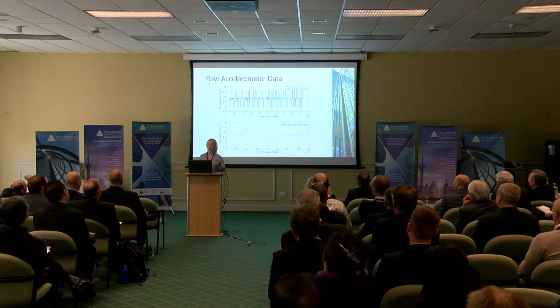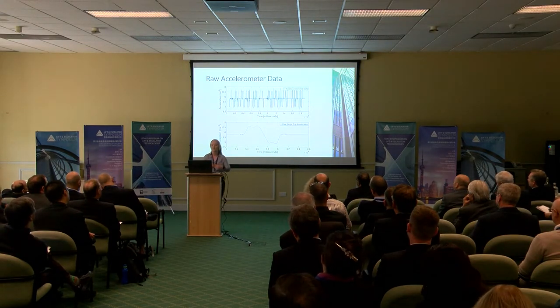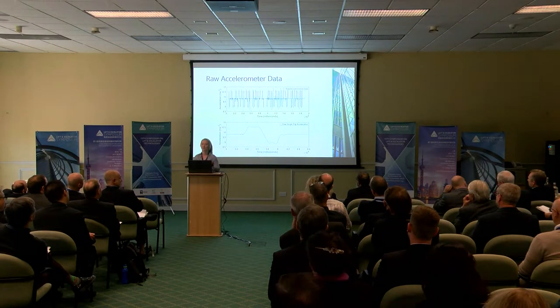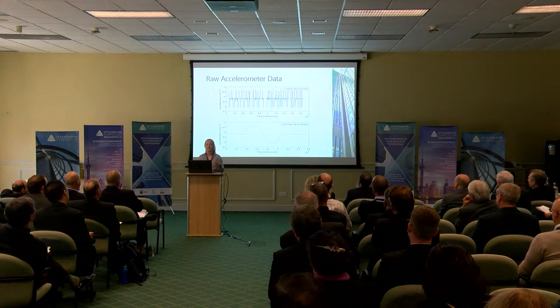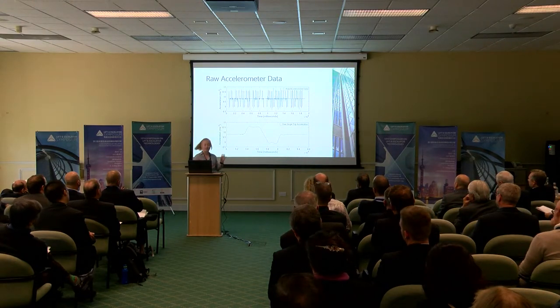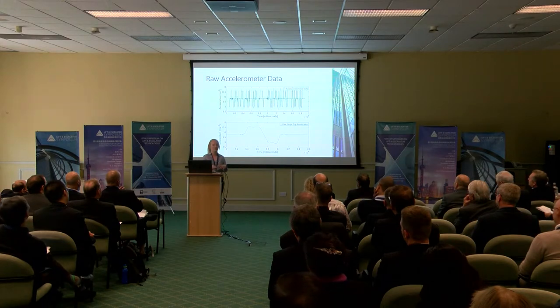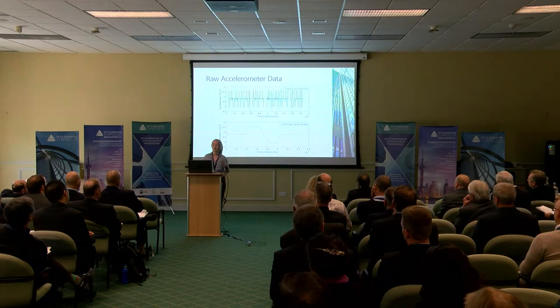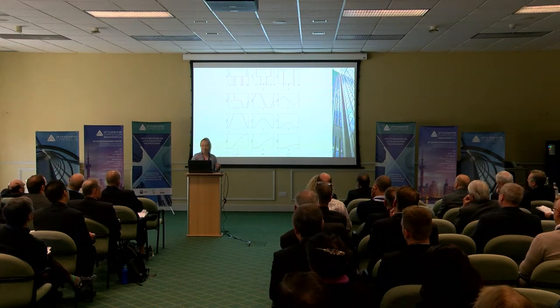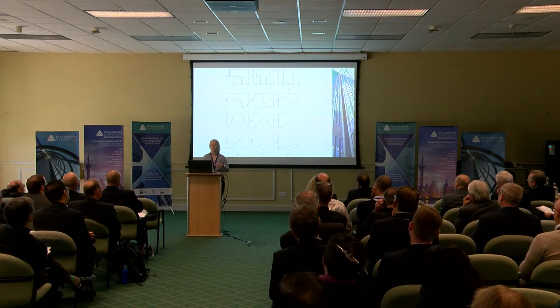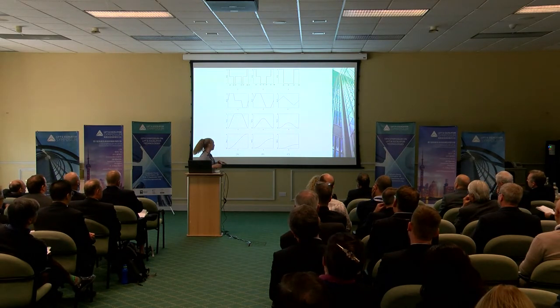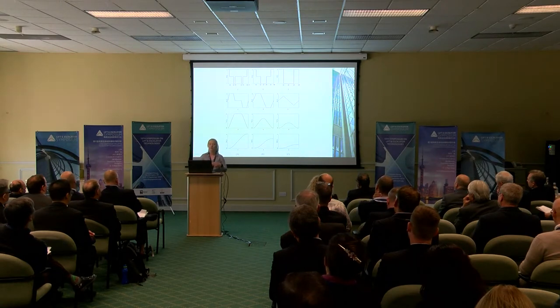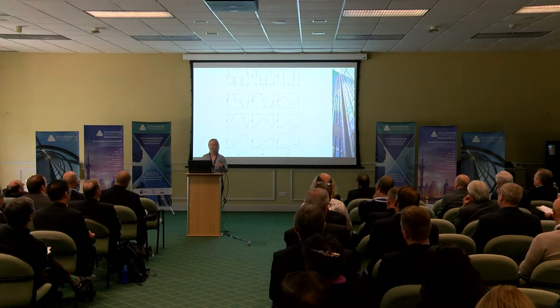The software was developed to accurately process a full set of raw accelerometer data, similar to that shown in the top image. To simplify the problem, the dataset can be isolated into a series of single up and down lift trips that can each be analysed individually. The lower image is an example of a single up trip isolated from the full dataset. The software will best-fit the ideal kinematics curves to the raw accelerometer data, then integrate and differentiate to find the corresponding jerk, velocity, and displacement profiles. Ideal lift kinematics represents a lift acceleration profile by a series of straight lines, so the software applies a linear regression method to fit the raw measured data to the ideal plot.